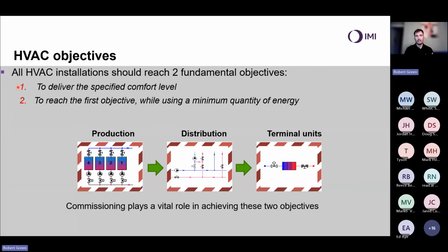We aren't going with excess flow on the pumps, excess pump head, all of these things. And commissioning is going to play a vital role in achieving this, because to get that second one, the system must be set up correctly. And in reality, where we're looking at really with the commissioning is this distribution side. How are we distributing the flow throughout an HVAC installation to ensure all areas are satisfied and they are only satisfied to their minimum requirements? We're not over satisfying, we're not overcooling or overheating.